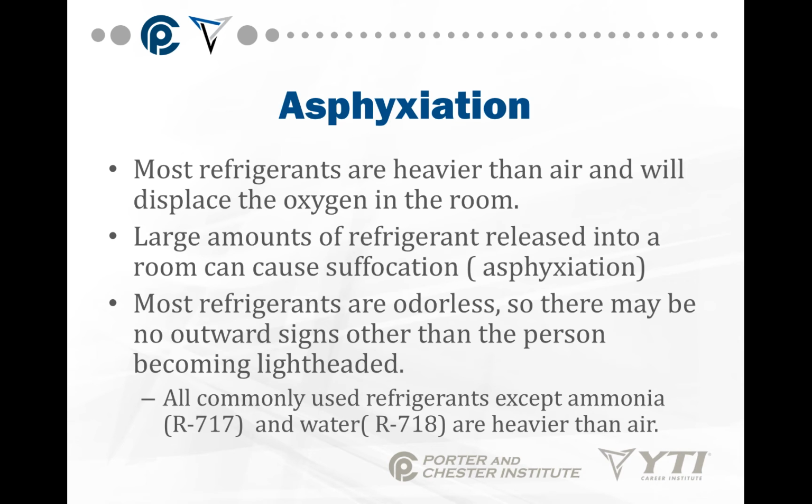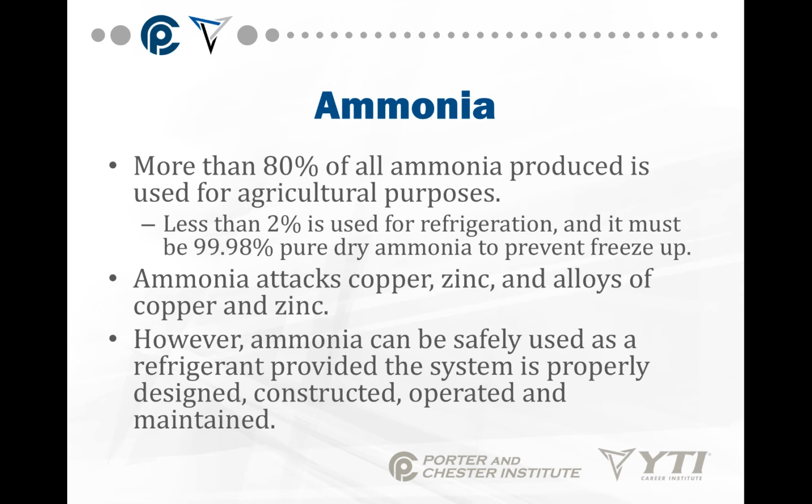The other thing you have to worry about is asphyxiation. Most refrigerants are heavier than air and will displace the oxygen in a room. Large amounts of refrigerant released into a room can cause suffocation, which is asphyxiation. Most refrigerants are odorless, so there can be no outward signs other than the person becoming lightheaded. Okay, all commonly used refrigerants except R717, which is ammonia, and water, R718, are heavier than air.